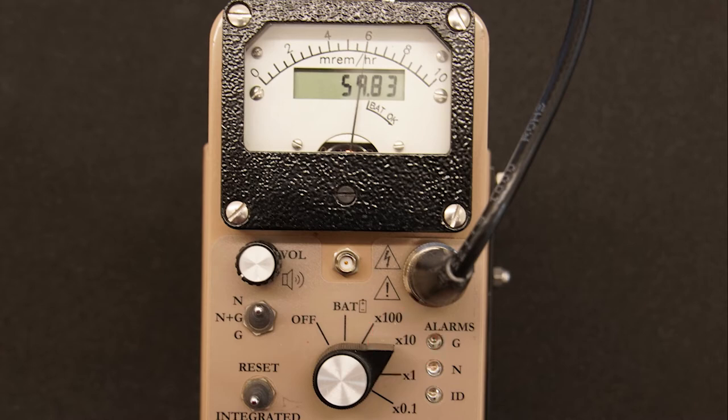In this example, the range switch is on the times 10 setting and the meter is indicating 6. So, the actual reading is 6 multiplied by 10, which equals 60 mrem per hour.